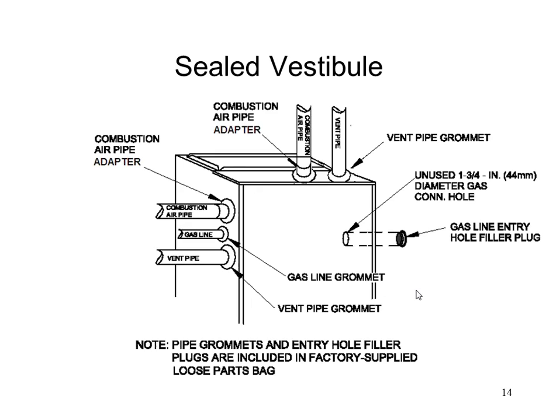Because once you take that top panel off, you are in the burner compartment. There's no separate enclosure for the burner compartment. So the whole top half of the furnace is technically your combustion vestibule. So everything does need to be sealed coming in, which means any penetrations that you make into the furnace for your gas pipe or electric or whatever it is need to be sealed. Otherwise, you won't be pulling air from your combustion pipe. You'll be pulling it from the room. We'll talk about that in a minute. But all those grommets for those penetrations do come in the loose part bag, so you don't have to buy anything extra. You just got to remember to put them on. So when you bring the gas line in, make sure you put the grommet on and so forth.